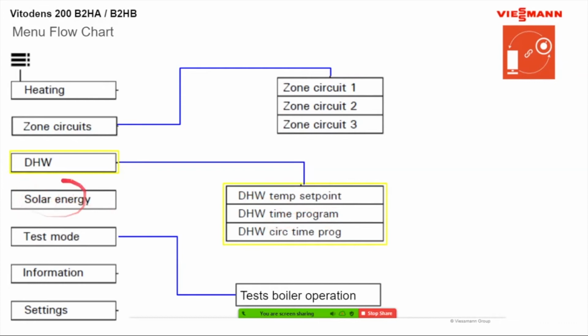If you were doing solar and you had a solar control connected to the boiler, you would see a submenu for your solar as well. So remember, that's auto recognized as well. Mixing valves are auto recognized, so you would see all of that as well, the temperature set points for your mixing valves.